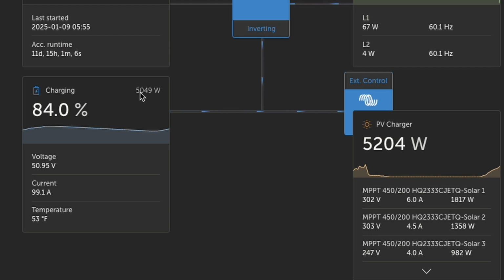Some really basic information here. This 5,000 watts is the charge current that's currently going into the battery. Voltage is the current battery voltage, the amount of current that's going in the battery, and the battery temperature. This is a system that's stored outside. This 53 degrees Fahrenheit, it's in a building, but it's not a heated building. Plenty of temperature to maintain charge and discharge, and this is kind of the overall battery bank average.